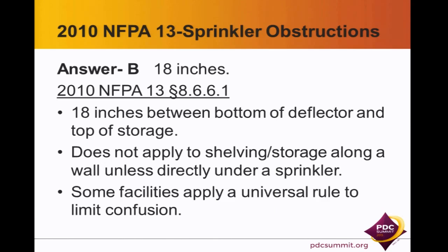Yeah, so NFPA 13 does permit storage against, or shelving and storage against a wall, as long as it's not directly under a sprinkler. I realize that operationally this might be confusing to staff members. A lot of times you see the red stripe painted around the entire wall, so some facilities do apply that universal rule just to limit any confusion.